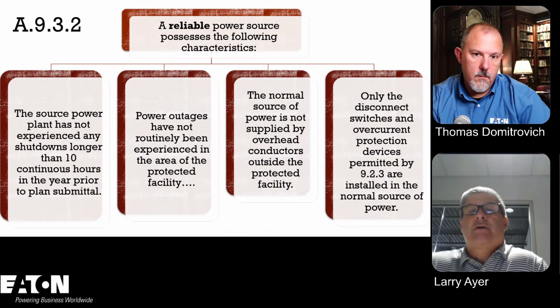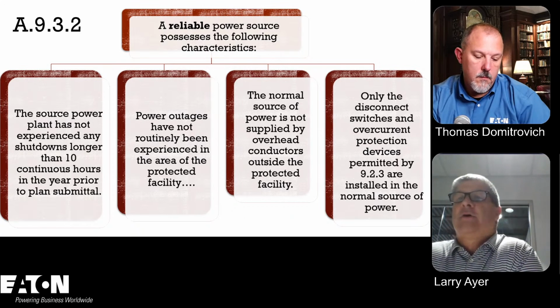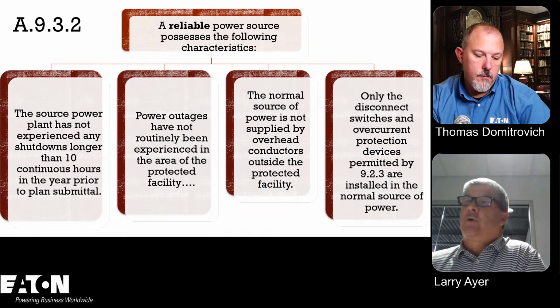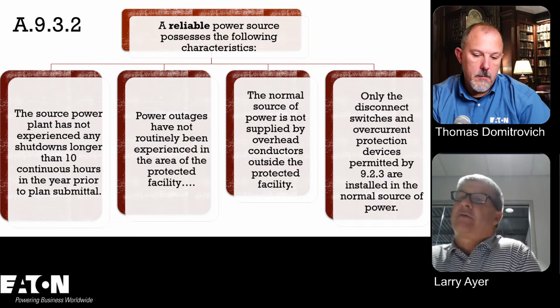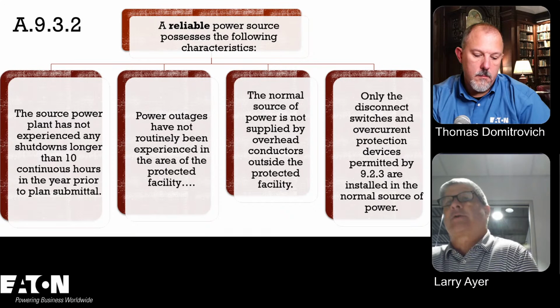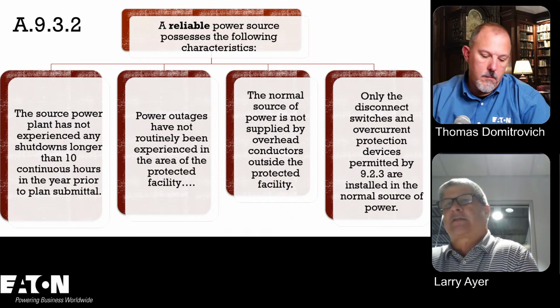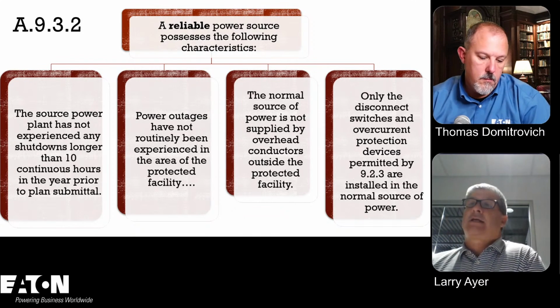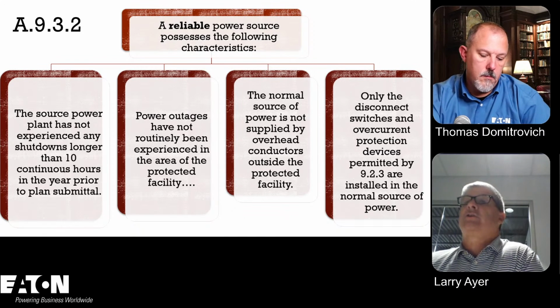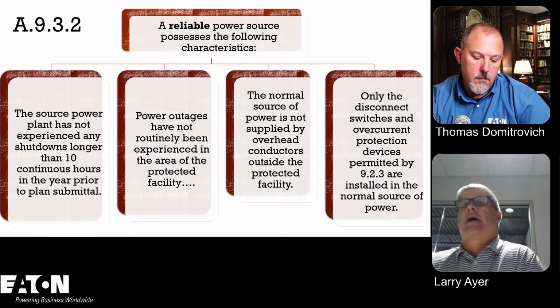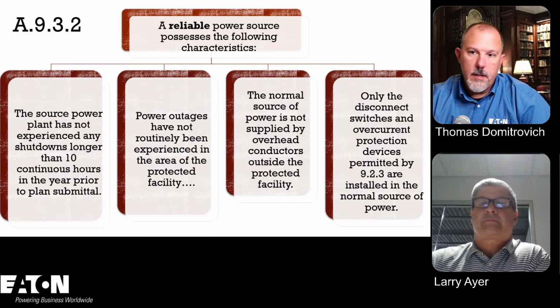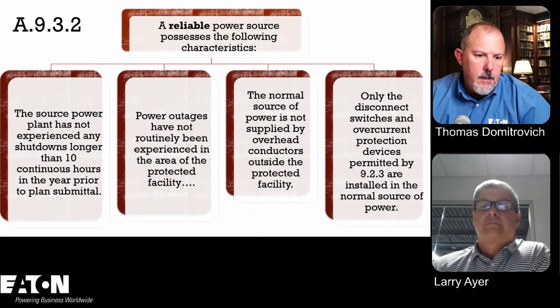And the last one is that only the disconnect switches and overcurrent protection devices are installed in the normal source of power. Typically, with a fire pump you're only allowed to have one disconnect between the service conductors and the fire pump. If you have more than one for some strange reason, you have to consider it not reliable, because someone can turn those off or some overcurrent devices can trip. So at least NFPA 20 does give you some criteria that you can use to help make your judgment about whether you need an alternate source. Yeah, excellent. All right.